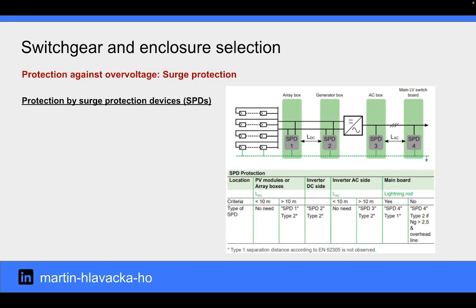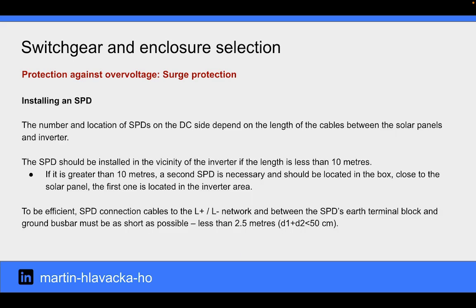On this slide, you can see a table for easy selection of SPD either for the DC or AC side of the PV system. The number and location of SPDs on the DC side depend on the length of the cables between the solar panels and inverter. The SPD should be installed in the vicinity of the inverter if the length is less than 10 meters. If it is greater than 10 meters, the second SPD is necessary and should be located in the box close to the solar panel.